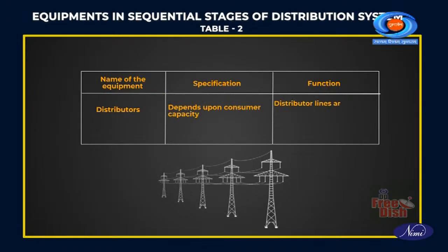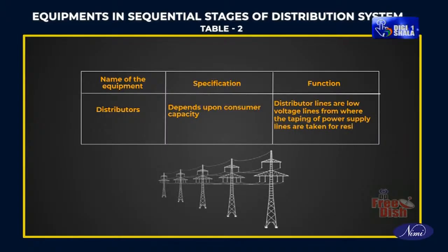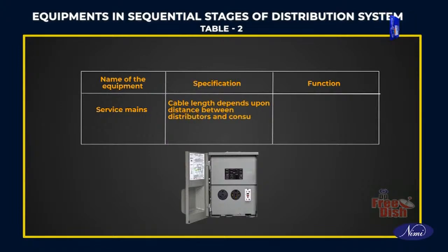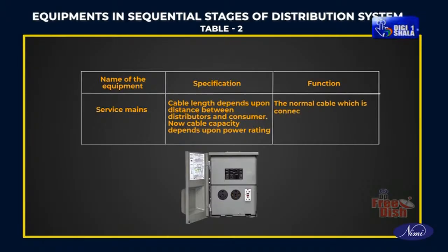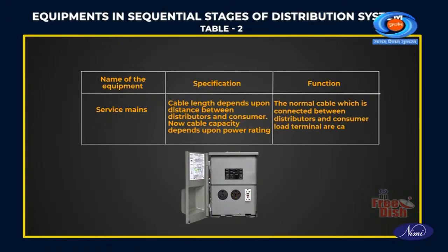Distributor lines are low voltage lines from where the tapping of power supply lines are taken for residential and commercial use. Service mains. Cable length depends upon distance between distributors and consumer. Now, cable capacity depends upon power rating. The normal cable which is connected between distributors and consumer load terminal are called service lines or service mains.